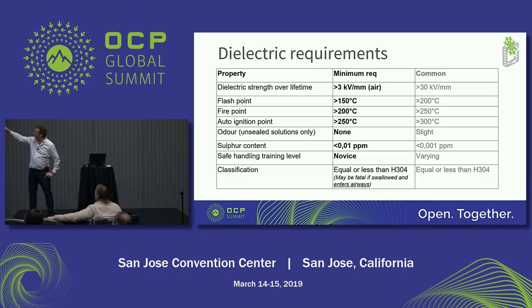So if you read carefully, it also states dielectric strength over lifetime. So you could conceive an immersion environment that lasts for 20 years, starts out with 50 kilovolts per millimeter and ends up at 3.5 kilovolts per millimeter, which is qualified. It's done its job. So yeah, but that's indeed the point.